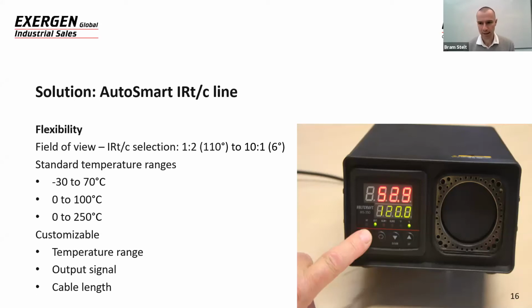We calibrate this on the AutoSmart transmitter in 3 standard temperature ranges. You can select from these. So you can select -30 degrees C to 70 degrees C, 0 to 100 degrees C, or 0 to 250 degrees C. Those are the options. But it's also very easy to customize it. In the demo, we will show you how that works. But this temperature range can easily be customized for specific applications.